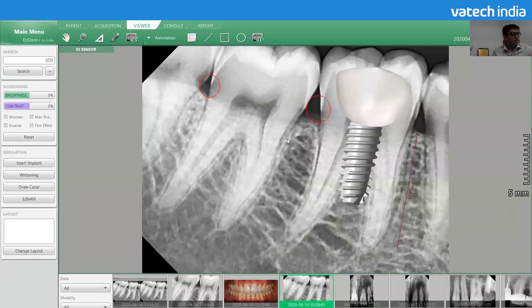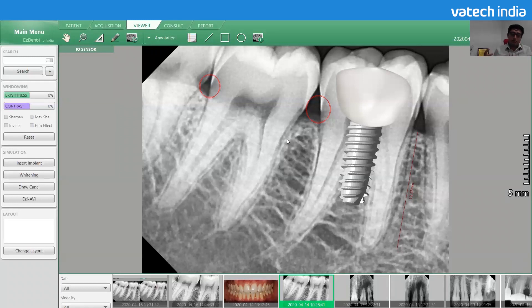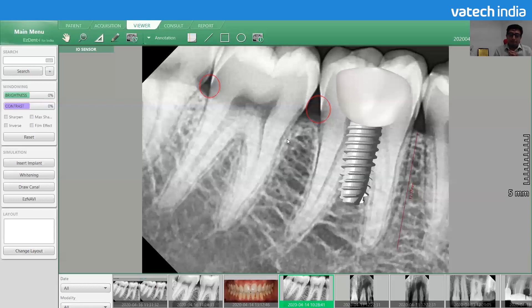These are intra-oral X-ray images. In intra-oral X-ray images, the source and detector are different machines. In OPG or CBCT, the detector and source are in the same machine — we know the angle at which the X-ray is bombarded, so we can calibrate and get the actual measurement. But with intra-oral X-ray images, the source and detector are different machines, so every image will have a different angulation effect and a different measurement.